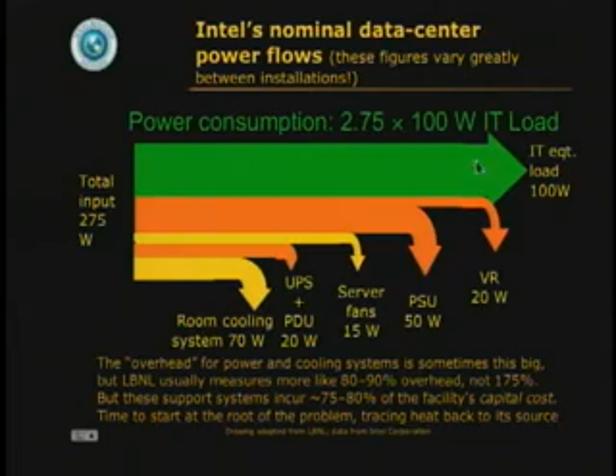Intel says that nominally, if you have 100 watts of IT equipment load, you have to add another 175 watts for the power supply, cooling, and air handling. That number varies a lot. Lawrence Berkeley typically measures 80 or 90% rather than 175% overhead. But these support systems for power supply and cooling run about 75 or 80% of the facility's capital cost. So squeezing these out by starting at the root of the problem, where the heat comes from the IT equipment, is a very fruitful direction.